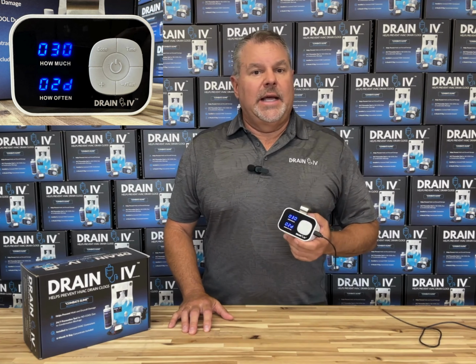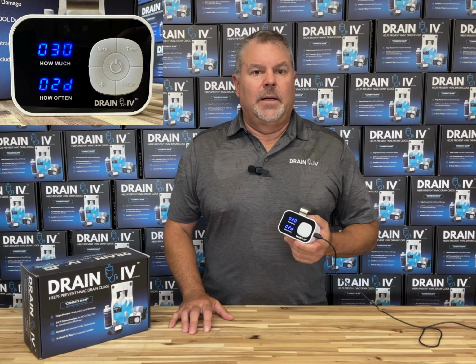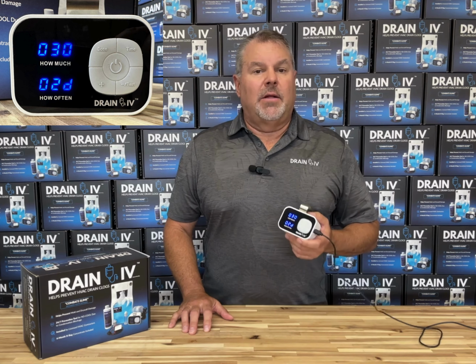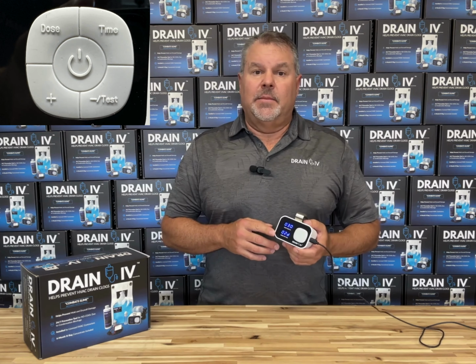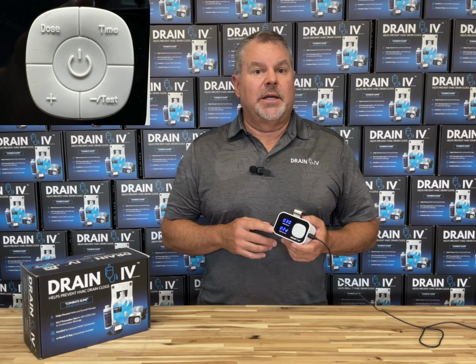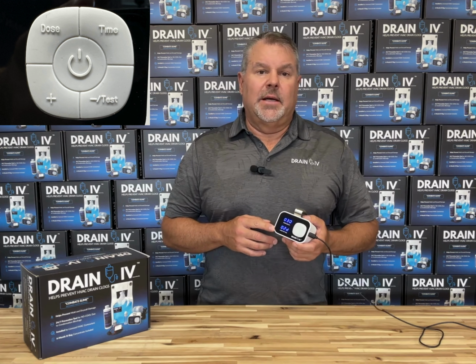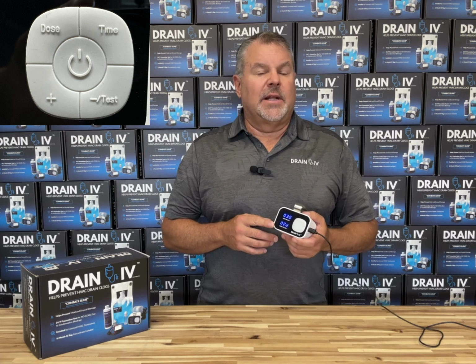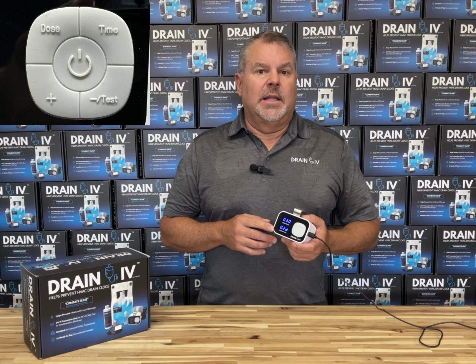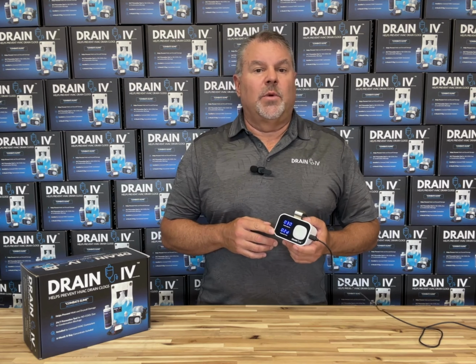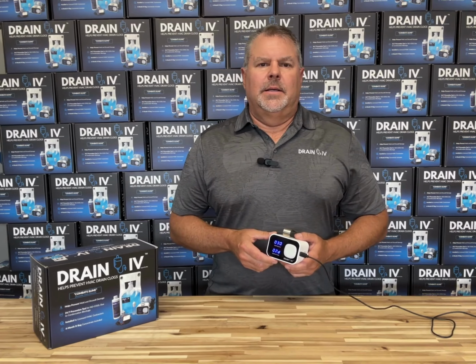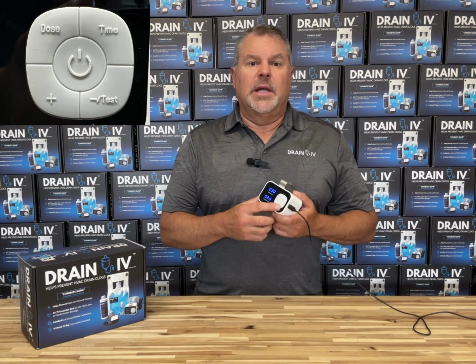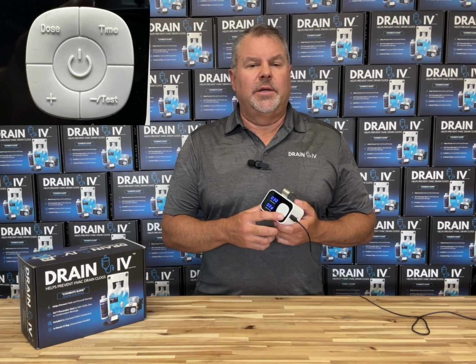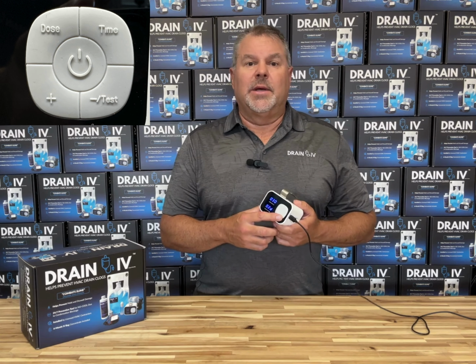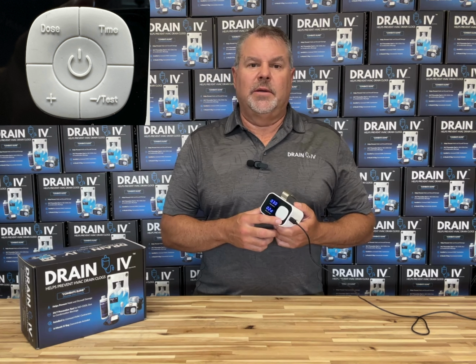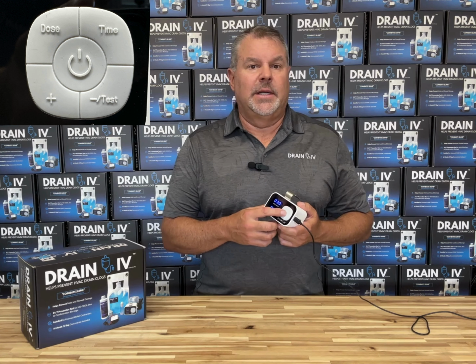Time is the frequency in days that the dose will be delivered. The time setting is displayed in how often. To adjust the time, single press time and use the plus and minus buttons. To confirm the setting, press the power button within 3 seconds of the last increment adjustment. The settings range from 1 to 30 days in 1-day increments. To test the program dose, double press the test button and the pump will run until the dose is delivered. You can cancel the test before the dose is completed with a single press of the power button.